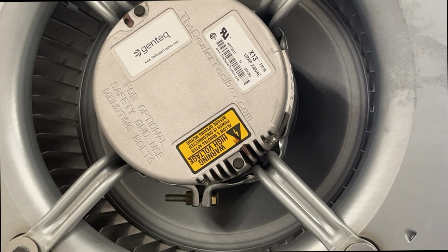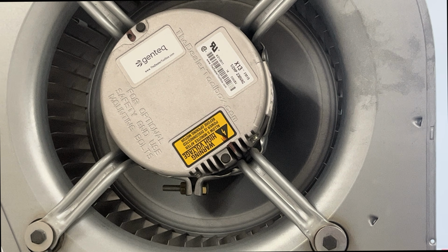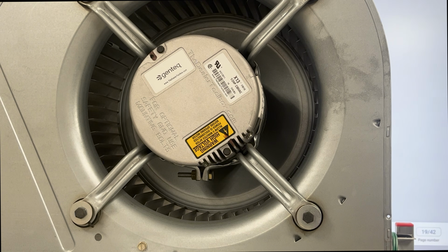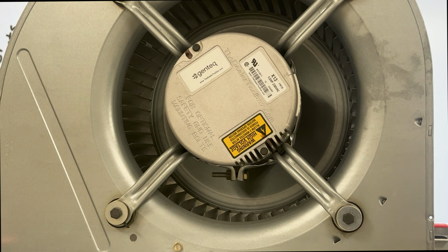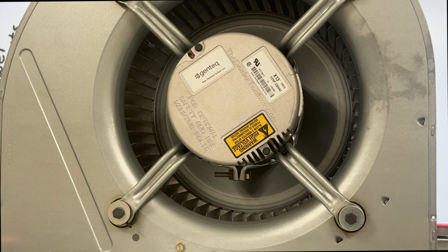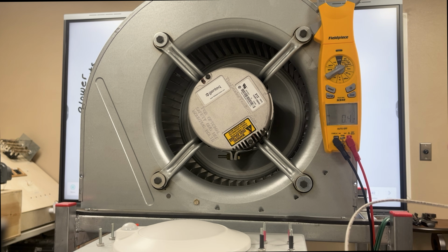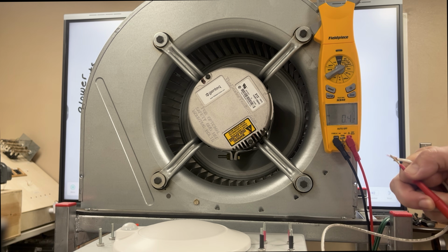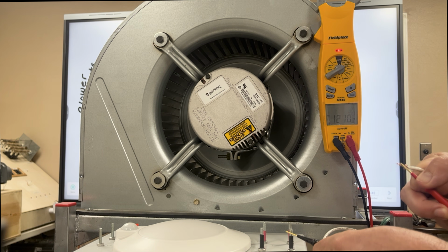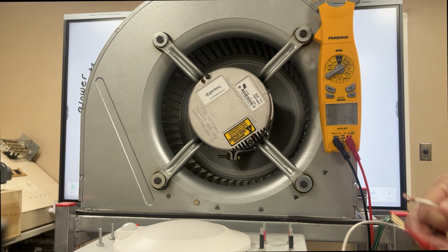Because I'm in a situation where it's in a lab and things have to remain safe, I'm going to pre-wire this and then turn the power on. So what we're going to do is first take out our extension cord, and we're going to plug into neutral. White wire and neutral. I'm going to see if I have a good neutral. We have 120. All right.